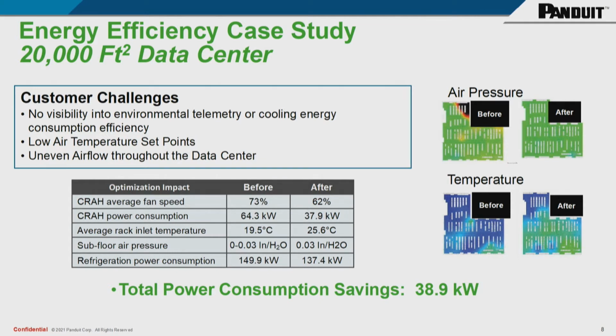They were overcooling, somewhere in the region of 19, but in the top left-hand corner of the facility there was a huge pressure drop, and that's where their high-density compute was actually sitting. That's a problem, because you want an even distribution. When you have pressure drops, you're creating inefficiencies, and that caused a huge problem for them in terms of the efficiencies they were seeing.